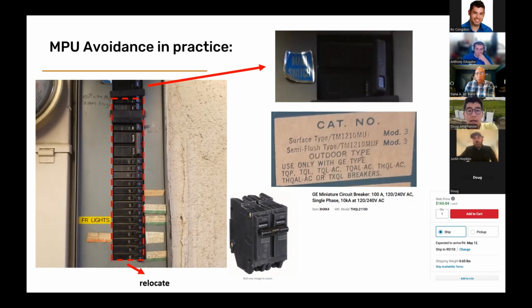There's NEC section 220, which covers load calculations. It gives you about 1 watt or half a watt per square foot for lighting and bedroom receptacles, like the ones you'd use to charge your cell phone, and those are usually on 15 amp or 20 amp breakers. There's no way you're going to plug in enough stuff to overload a 15 or 20 amp breaker - that's just the smallest size available. So there's a ton of headroom in these things.